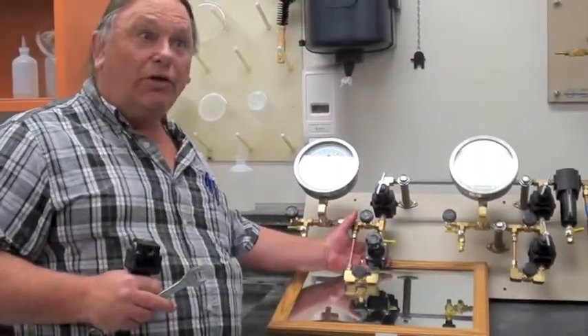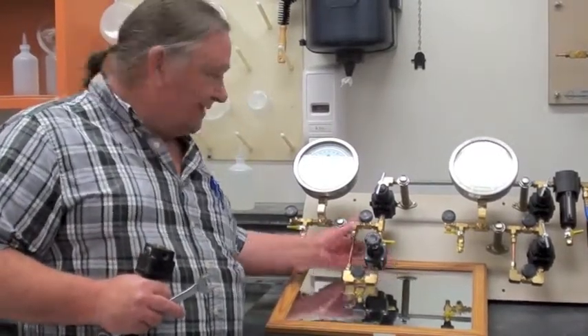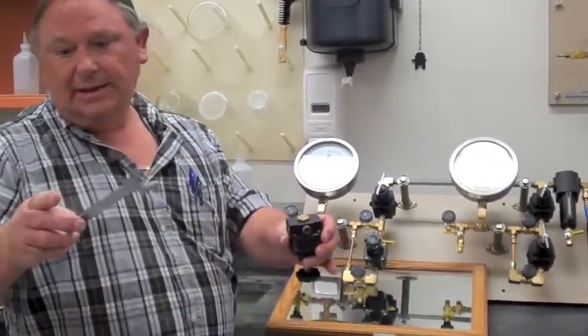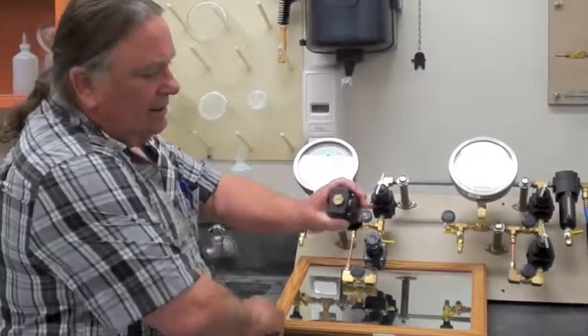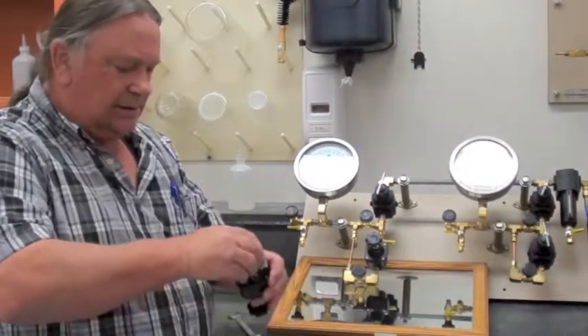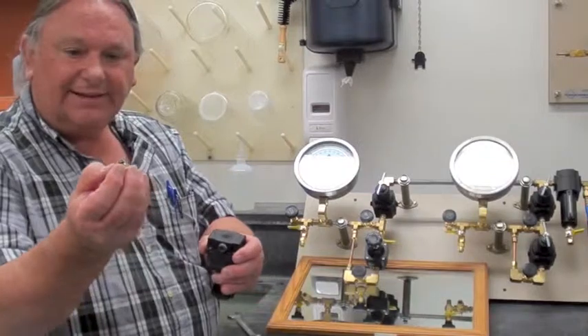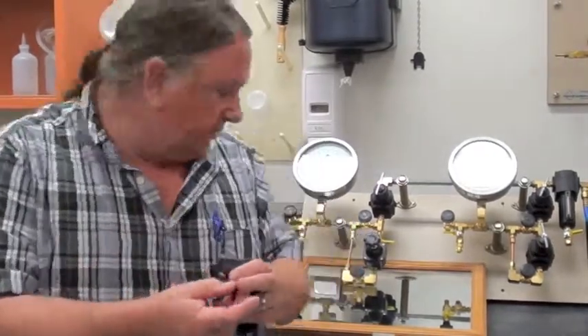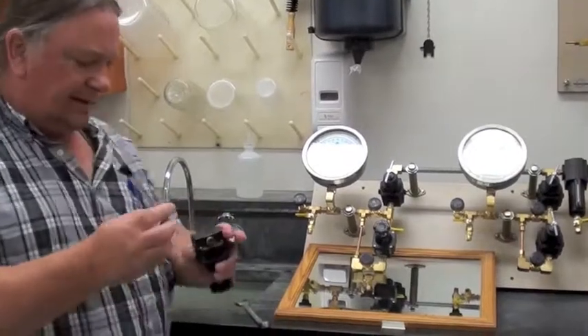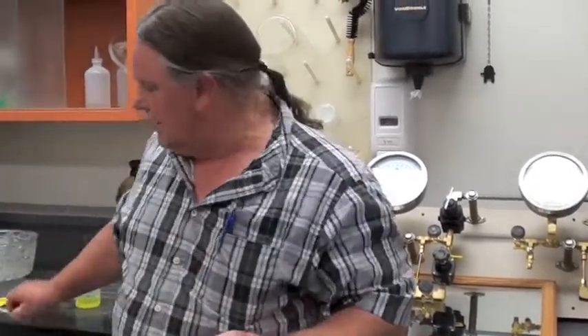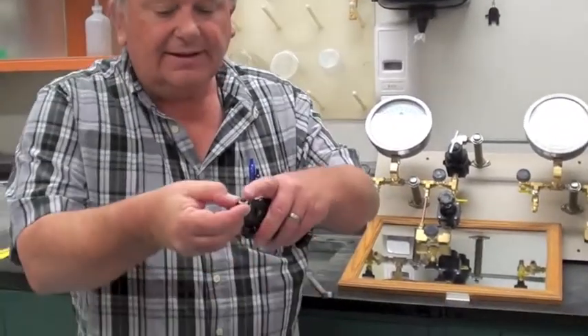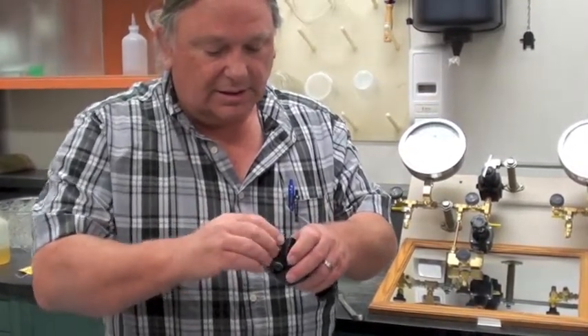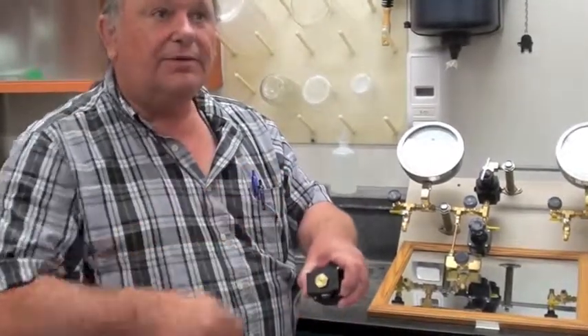Okay. If you ever get the situation where this is leaking all the time, that's off, that's off, and it's still leaking. The suspicion is that ram happened. The seat in the back came out. And I'll show you how to put it back on. Get a three-quarter inch wrench. Loosen the brass part. There's some plastic fittings on here. And if you look, you'll see a white washer on the bottom. That probably has moved out. So, then you'll need a wood dowel. Something to go in there. And press that seat back into place. Once the seat's back in place, check these parts here. Make sure that this isn't bent or cracked. Reassemble it. Retighten it. And it should be okay now.